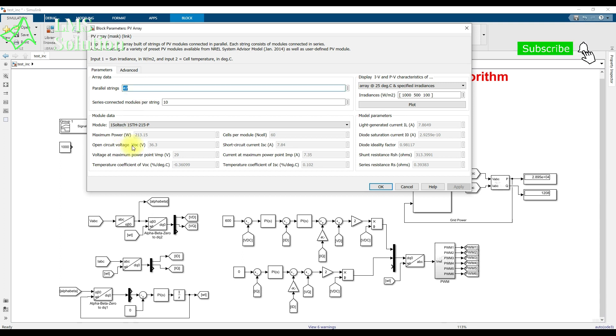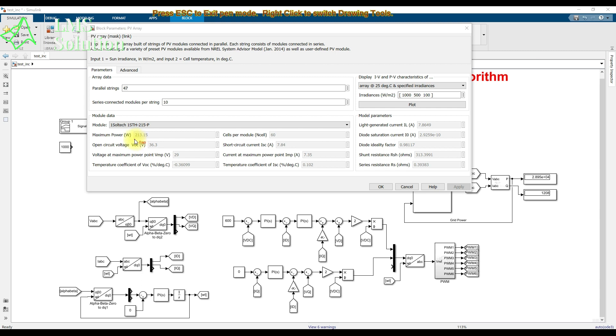The single panel power is 213.15 watts. The open circuit voltage is 36.3 volts, and the voltage at maximum power point is 29 volts. The short circuit current is 7.84 amps and the current at maximum power point is 7.35 amps.